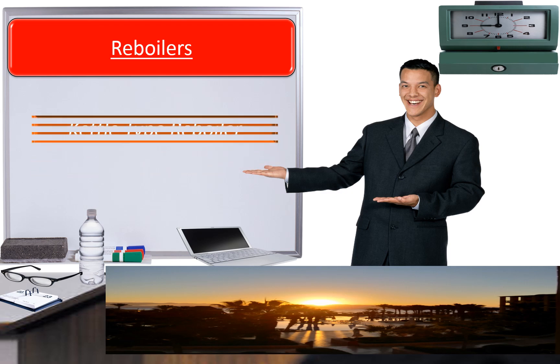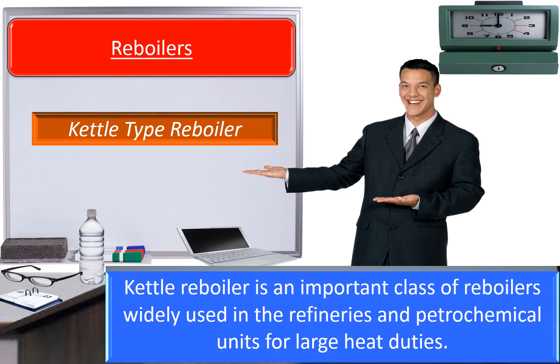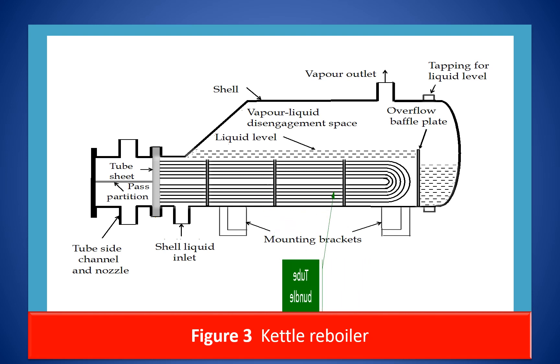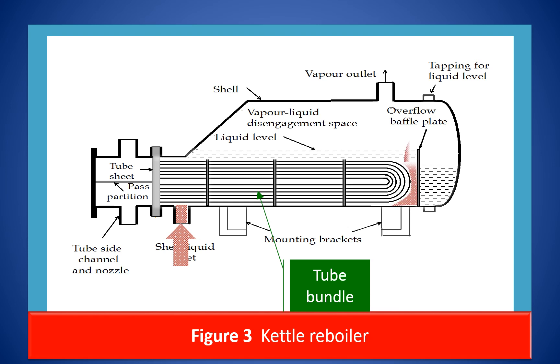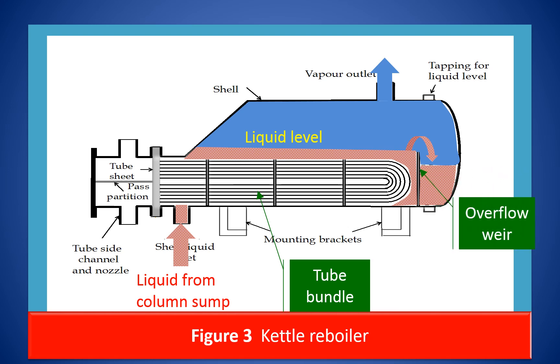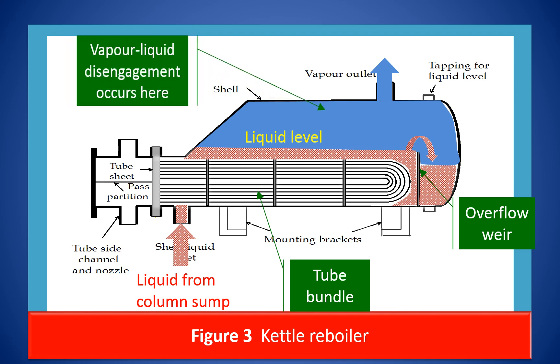Kettle type reboilers are an important class of reboilers widely used in refineries and petrochemical units for large heat duties. In a kettle type reboiler, the tube bundle is immersed in a pool of liquid in an oversized vessel. The submergence of the tube bundle is ensured by an overflow weir at a height of roughly 50 to 100 mm above the surface of the topmost tube of the tube bundle. The liquid flows from the column sump to the bottom of the kettle shell, where it is partially vaporized. The vaporized liquid is then separated from the liquid in a vapor disengagement space above the tube bundle.